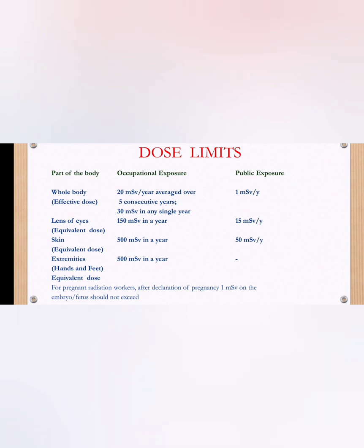Moving on to the lens of the eye: the occupational exposure limit for the eye lens is 150 millisieverts per year for radiation workers. For the public, the eye lens dose limit is 15 millisieverts per year.